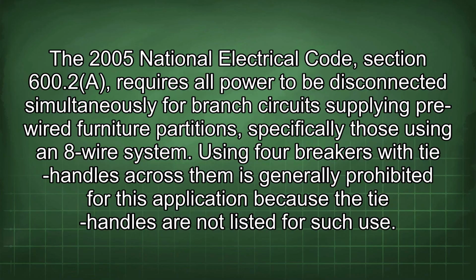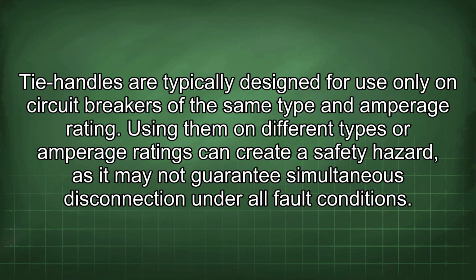2005 National Electrical Code, Section 600.2a, requires all power to be disconnected simultaneously for branch circuits supplying pre-wired furniture partitions, specifically those using an 8-wire system. Using 4 breakers with tie handles across them is generally prohibited for this application because the tie handles are not listed for such use. Tie handles are typically designed for use only on circuit breakers of the same type and amperage rating. Using them on different types or amperage ratings can create a safety hazard, as it may not guarantee simultaneous disconnection under all fault conditions.